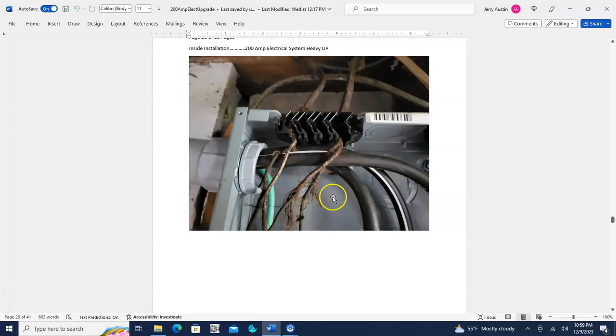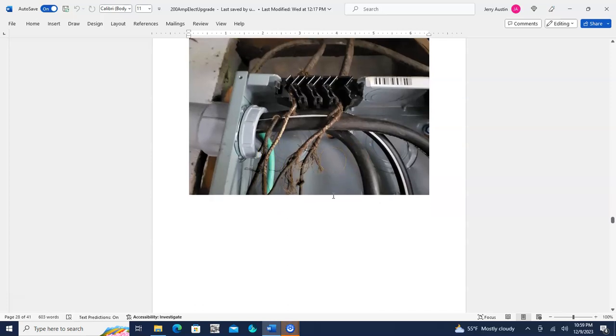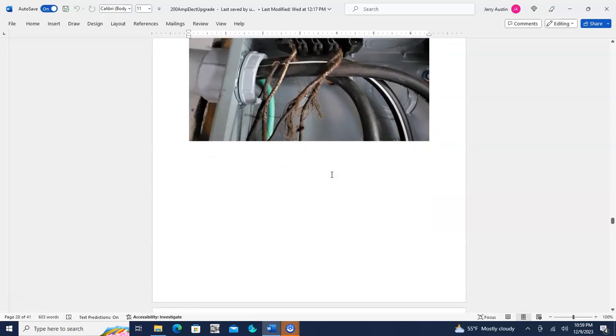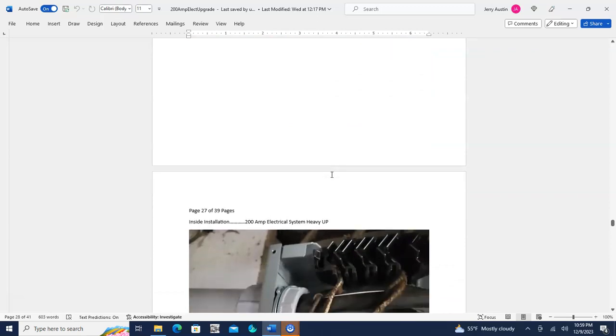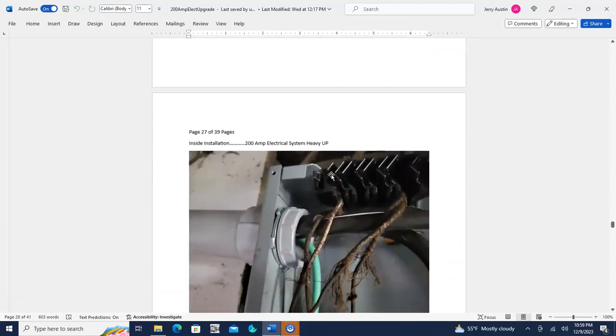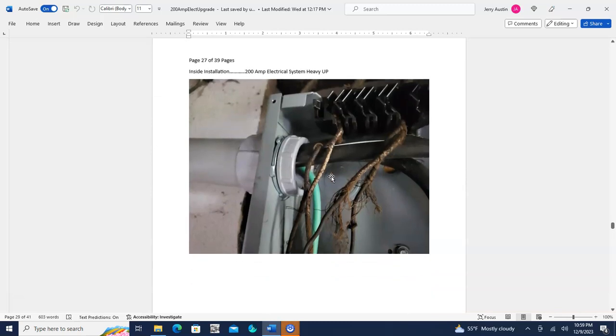It's on all of these newer systems, these 4-wire systems. Used to be there was a 3-wire system, and prior to that there was only a 2-wire system with no ground. And that's what we're upgrading from, the 2-wire system with no ground. We're upgrading that to this 4-wire system with the electrical ground plus also the safety ground. You can see this old wiring in this house. A lot of it is really frayed, so it's old wiring. It does not have any ground wires at all to it. So the house itself needs to have some new wiring run throughout the house.